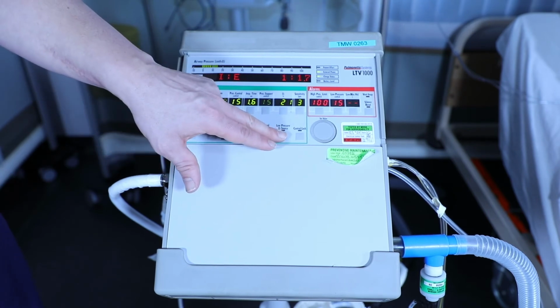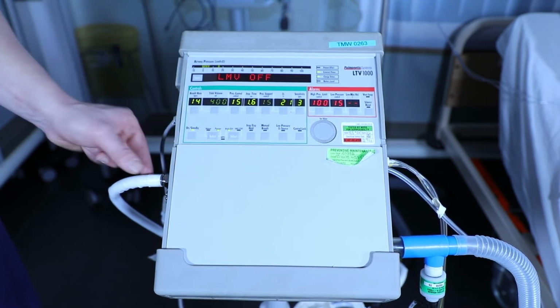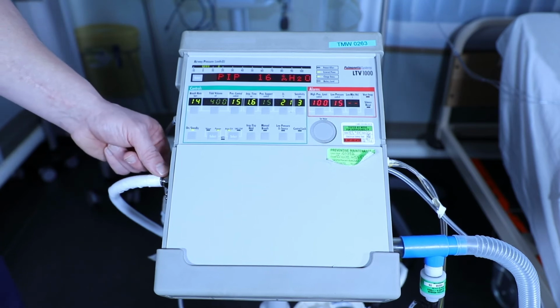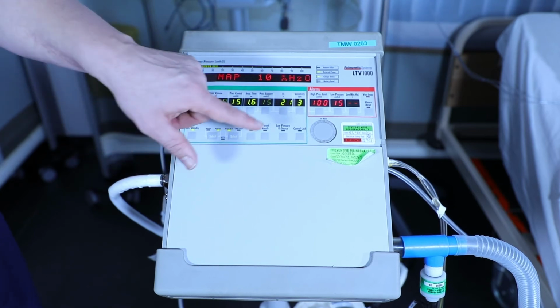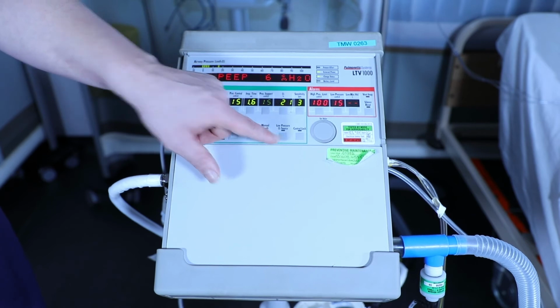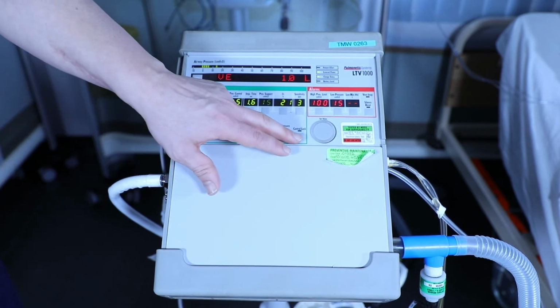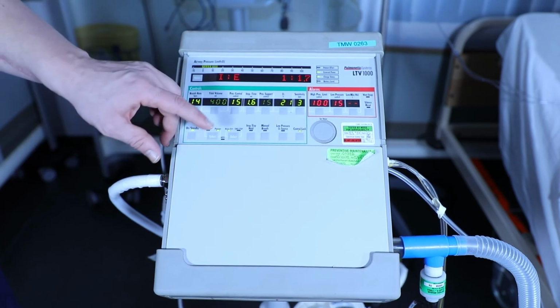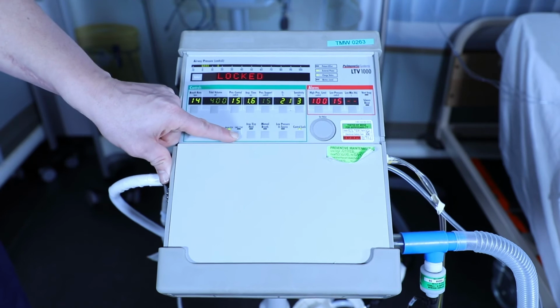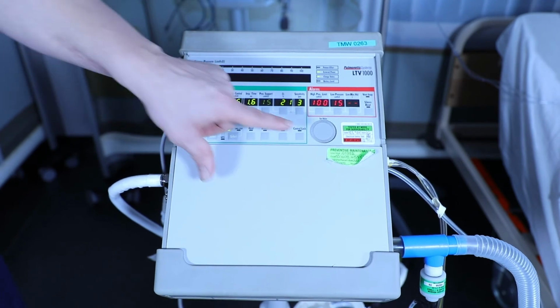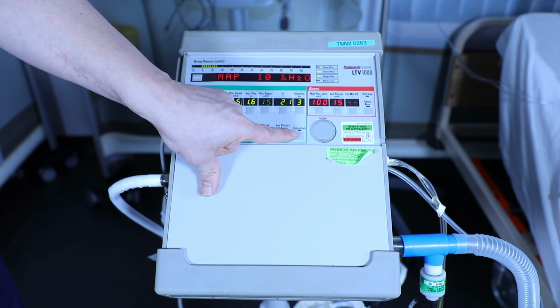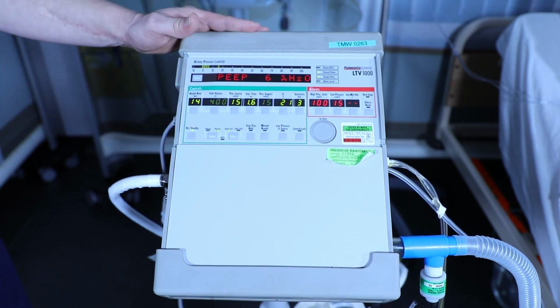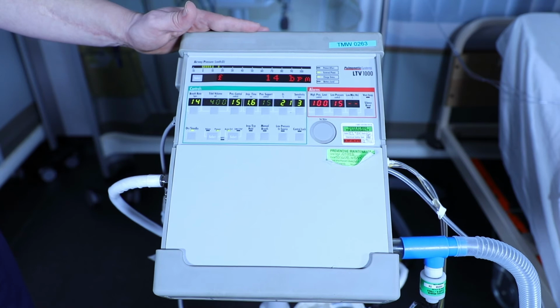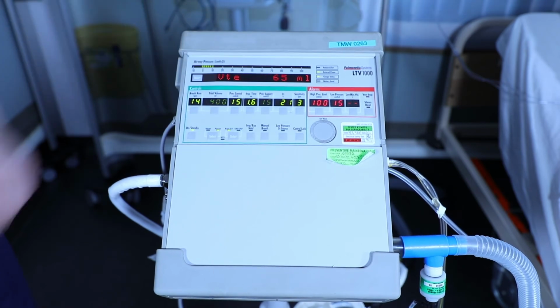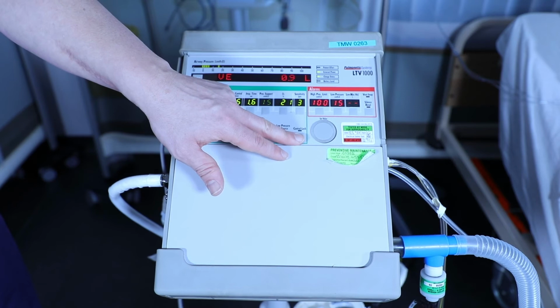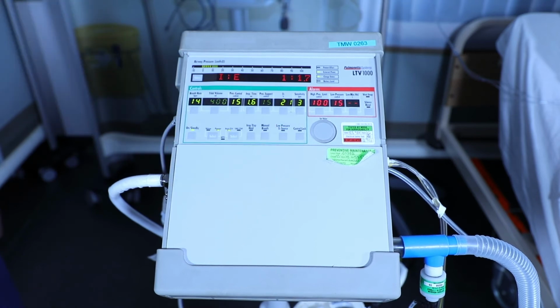We'll cover the low pressure O2 separately, but this, if we have a failure on our high pressure O2 hose, we can deliver oxygen through the low pressure O2 source. The control lock button just locks all of our buttons, so if we have this on and we try to change, we notice that it says that it's locked. To unlock this, we press the control unlock button, and because we've already preset this to control unlock set to easy, that allows us to do that with one click of the button. Alternatively, if it was on the hard setting, we would have to press and hold for 3 seconds.